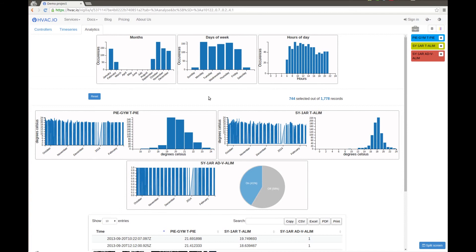So you can conclude that there is a schedule for this fan. Not only that, you can validate the schedule. You can see that it never worked at night for the entire six months of the data we have.